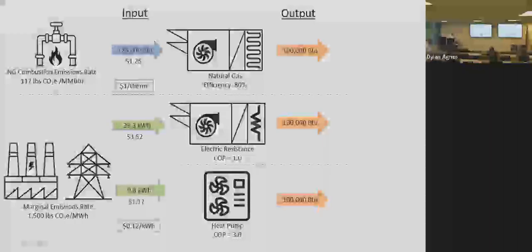What does it cost? Well, it costs this boiler or this furnace about $1.25 to deliver that therm. And that's based off of that 80% efficiency and that $1 per therm. It costs this electric resistance furnace about $3.50, so almost 3 times as much. So in this case, this definitely beats electric resistance in terms of cost. And then what is the heat pump, kind of marginal performance of 3.0? It does it at $1.17, so a little cheaper.